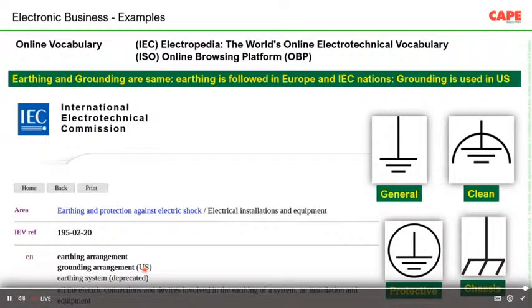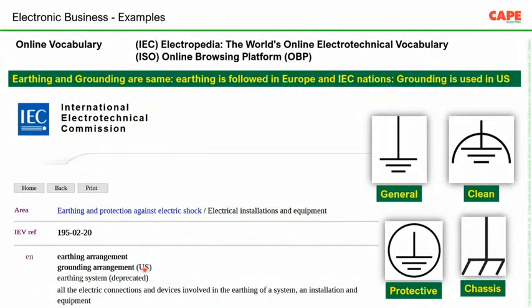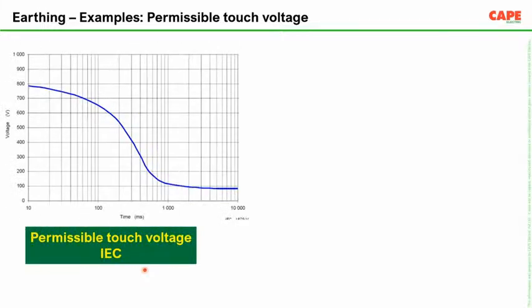...which has to be printed on an earth terminal of an equipment. Say for example, you have a sensitive electronic equipment, the clean earth is printed. So the meaning of this particular printing is that the equipment is sensitive to high frequency things, so you should have a clean earthing system or a functional earthing system.